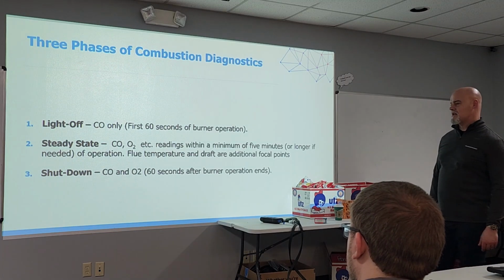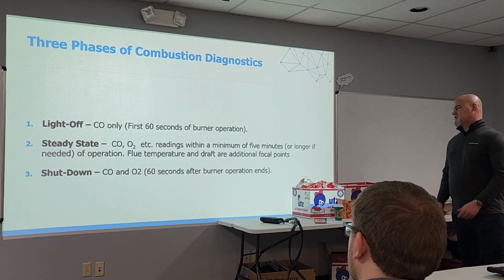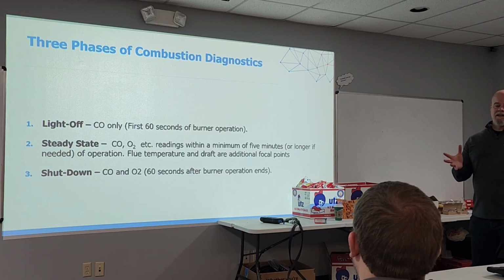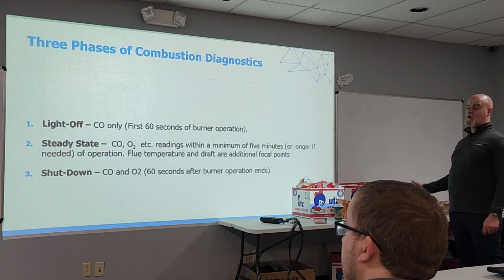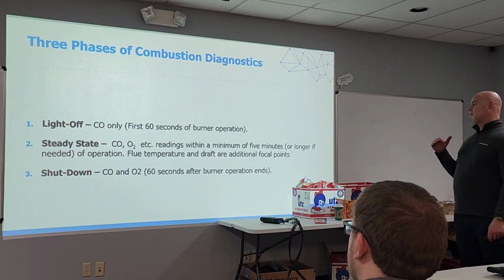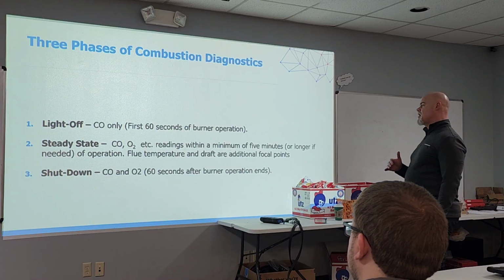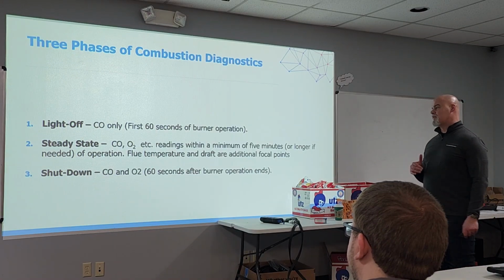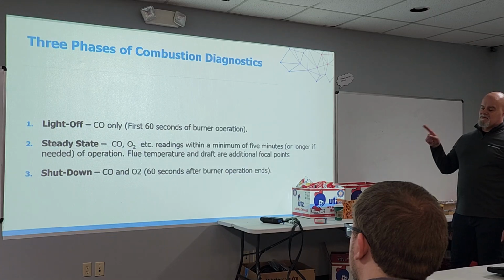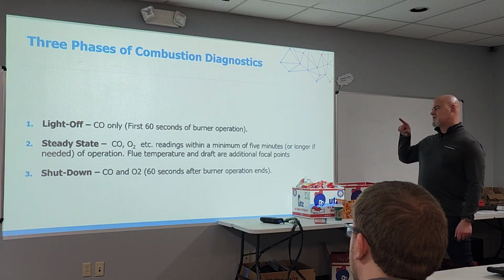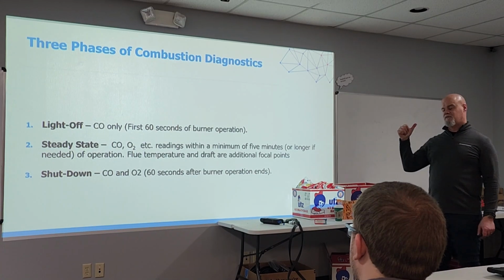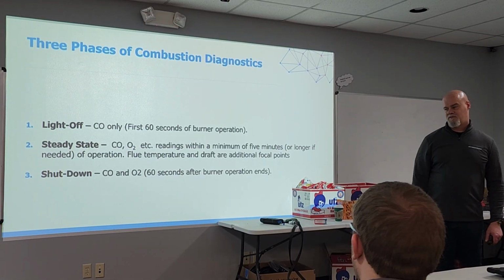Three phases of combustion diagnostics. If you attend an NCI class, you're going to learn a lot of this stuff, and they go heavily in depth on it. Light off: CO only is going to be your main focus, in the first 60 seconds of burner operation. Steady state: five minutes or greater system runtime. You're going to focus on CO and oxygen, stack temperature, and draft.